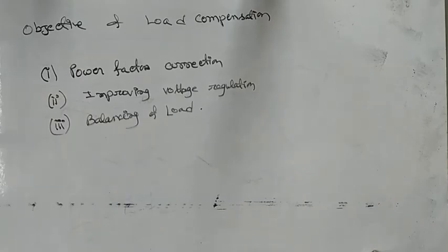Most of the real life loads operate in lagging power factor, that is they absorb reactive power. Since the reactive power generation sources are limited, there is a deficit of reactive power when the power system is heavily loaded, and this leads to voltage depression at the load bus, resulting in higher current intake by constant power loads.